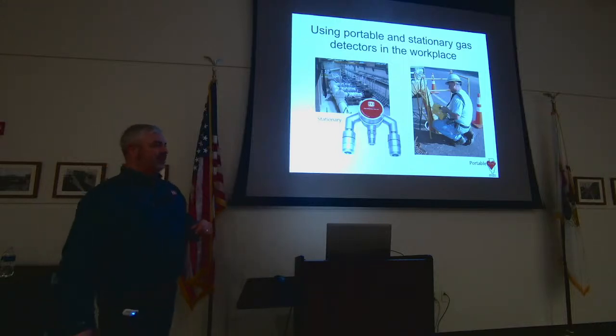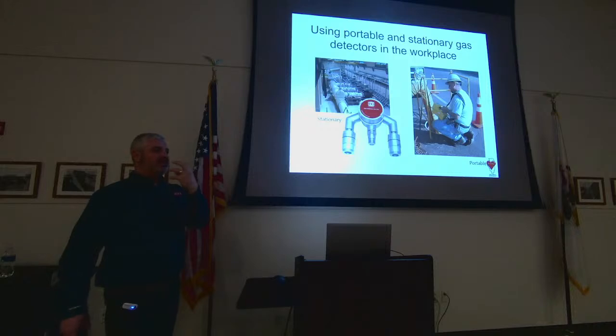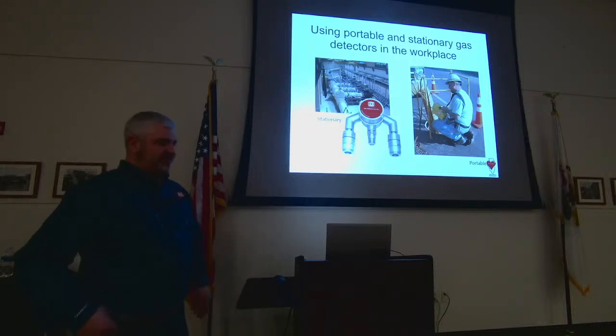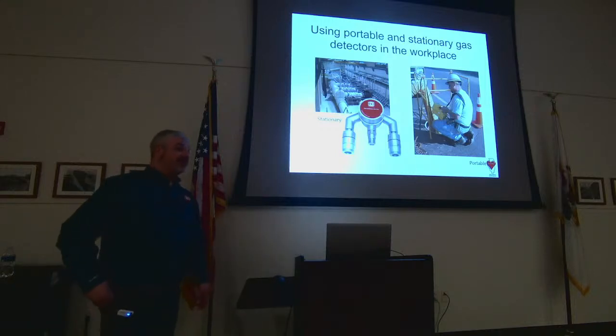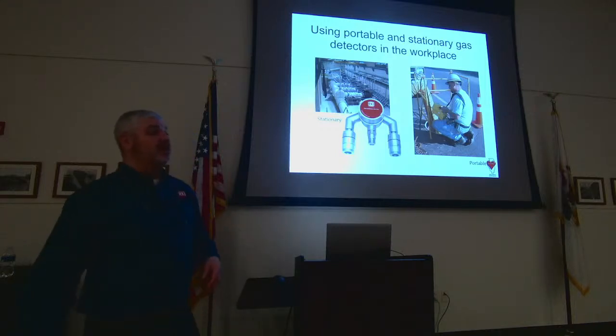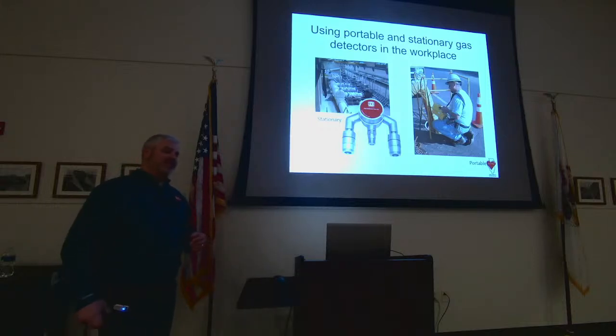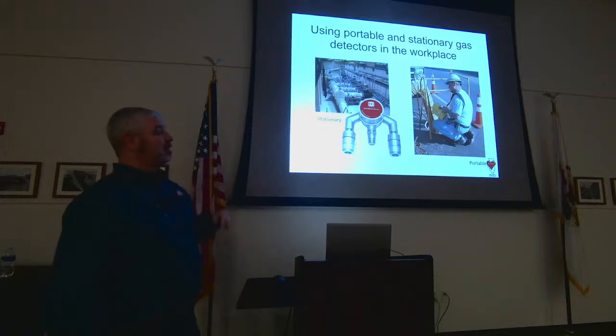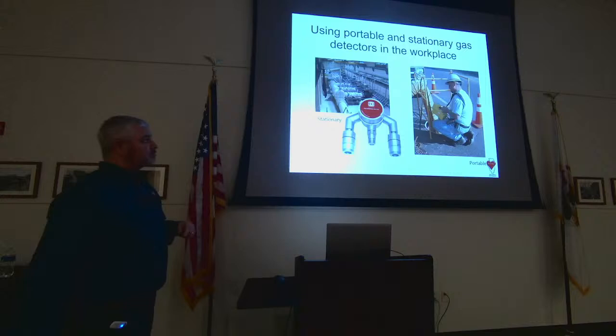What it's saying is, please wear these in your breathing zone. The idea is the instrument should recognize what the wearer is inhaling. So you don't want to wear a gas meter on your belt anymore - funny, because the first 15 years of my life, we called them belt clips and attached them to our belt. Recently, they've said we're more worried about what's being inhaled, so we place those meters higher, 10 to 12 inches in your breathing zone.